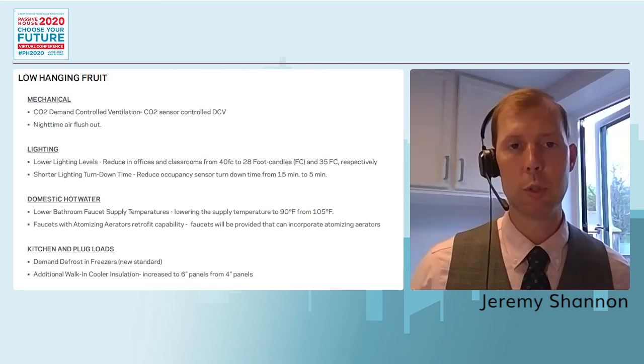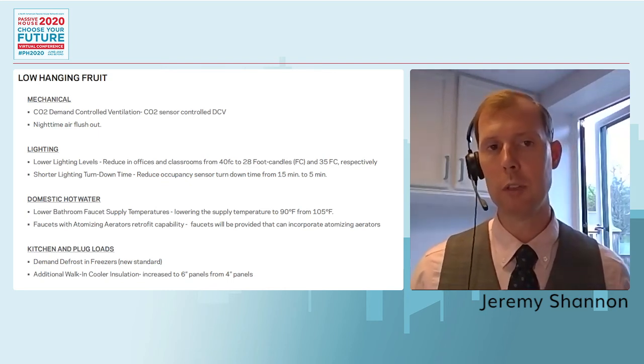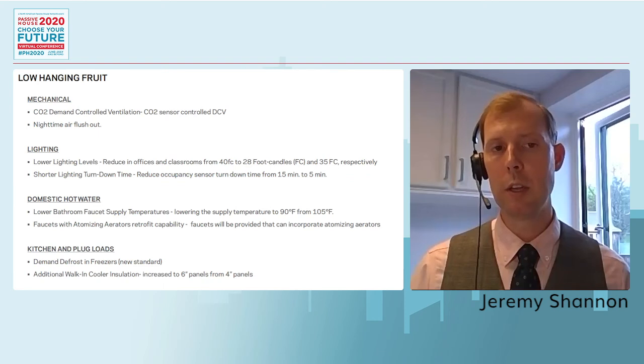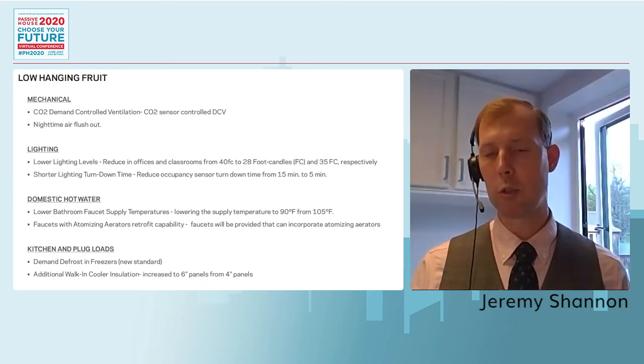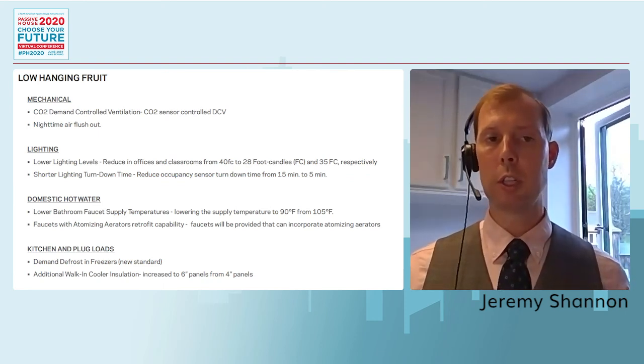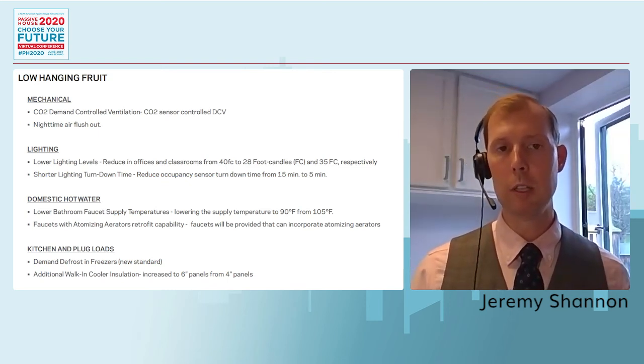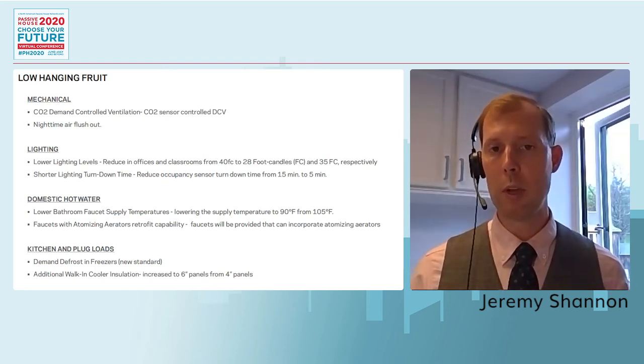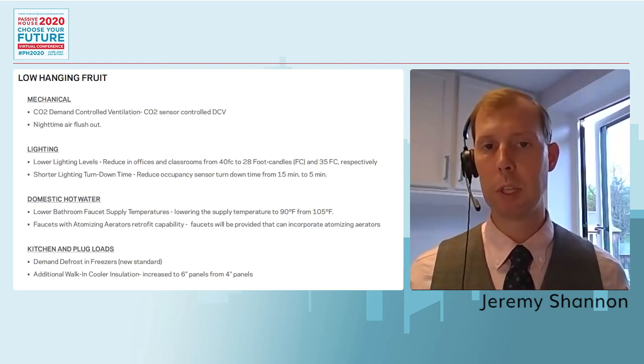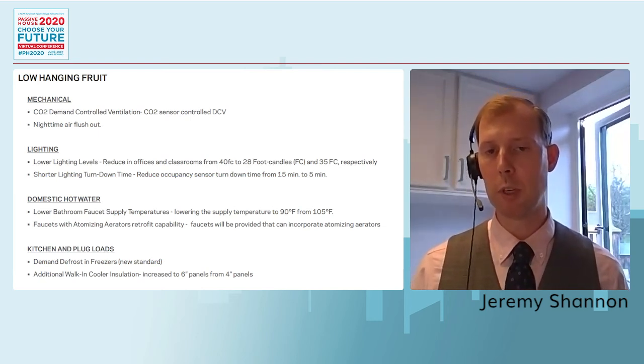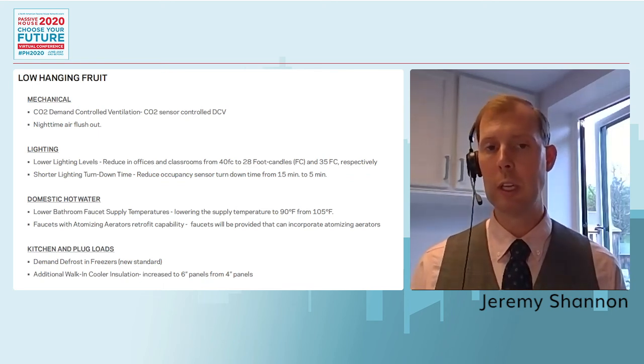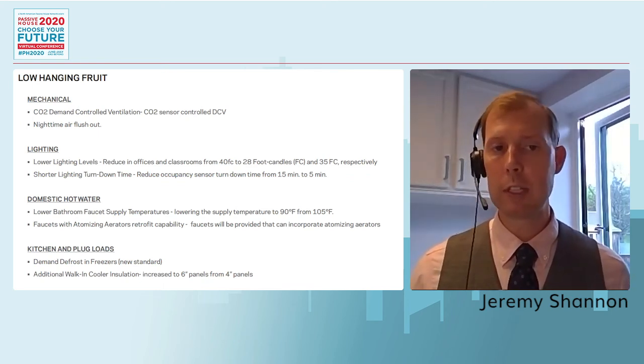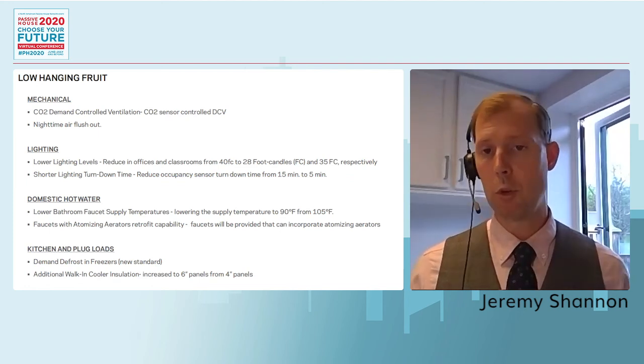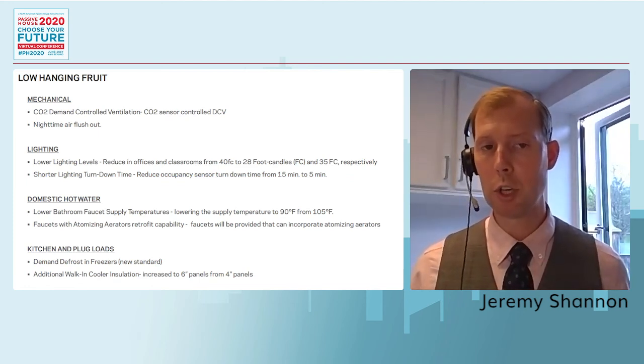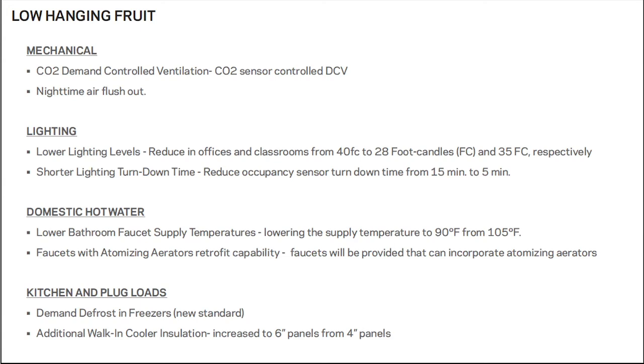So we were able to do some shifts, like the significant one of going from occupancy demand control ventilation, which is what we had before, to CO2 controlled demand ventilation. That really gave us a win, and it was an extremely nominal cost, really just the cost of the difference between an occupancy controller and a CO2 controller in a new building. Nighttime air flush out was another one. There's no cost, it's just a controls sequencing change. The lighting levels, again, no costs. We just needed to reprogram them.